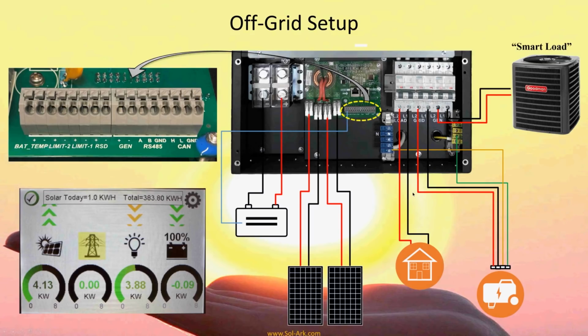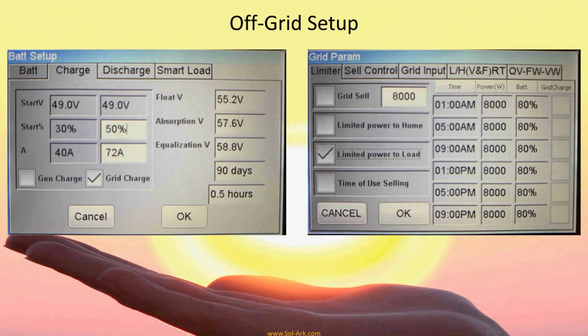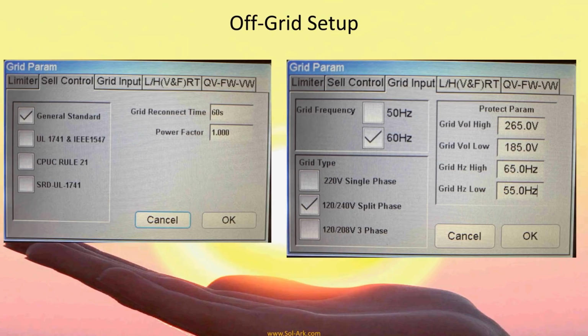Okay, so this is our off-grid setup, and we will want to also select some general limitations - we want to widen them. The reason we're selecting this is we don't want to use UL 1741, it's very, very tight in the frequency range. So we want to use some wide frequency parameters to allow us to go from 55 to 65 hertz so that it'll work with any generators.